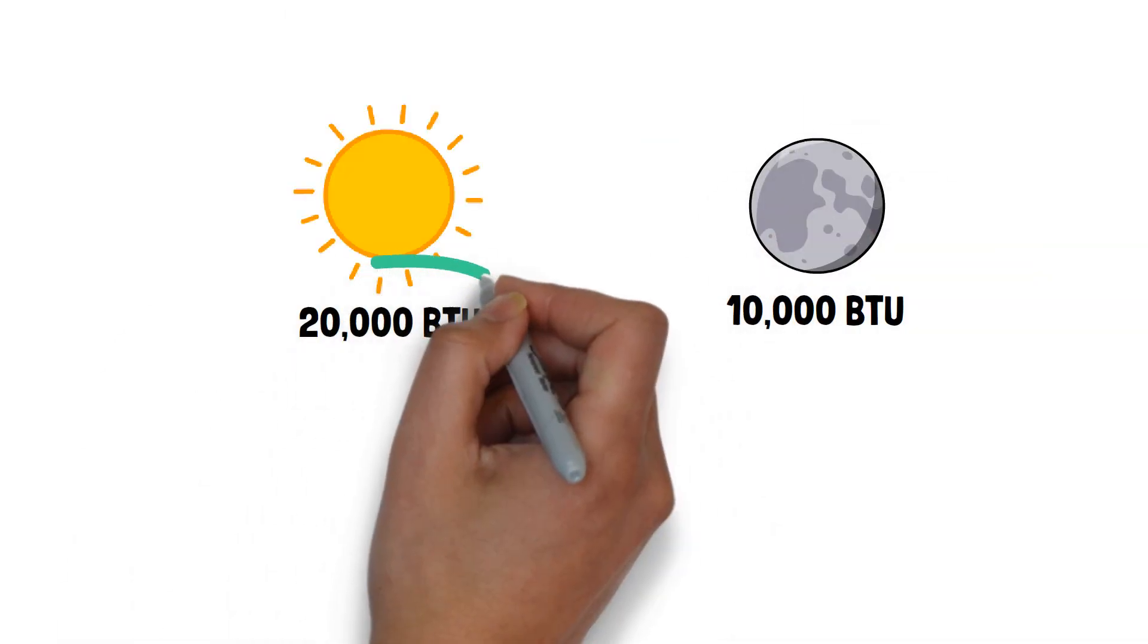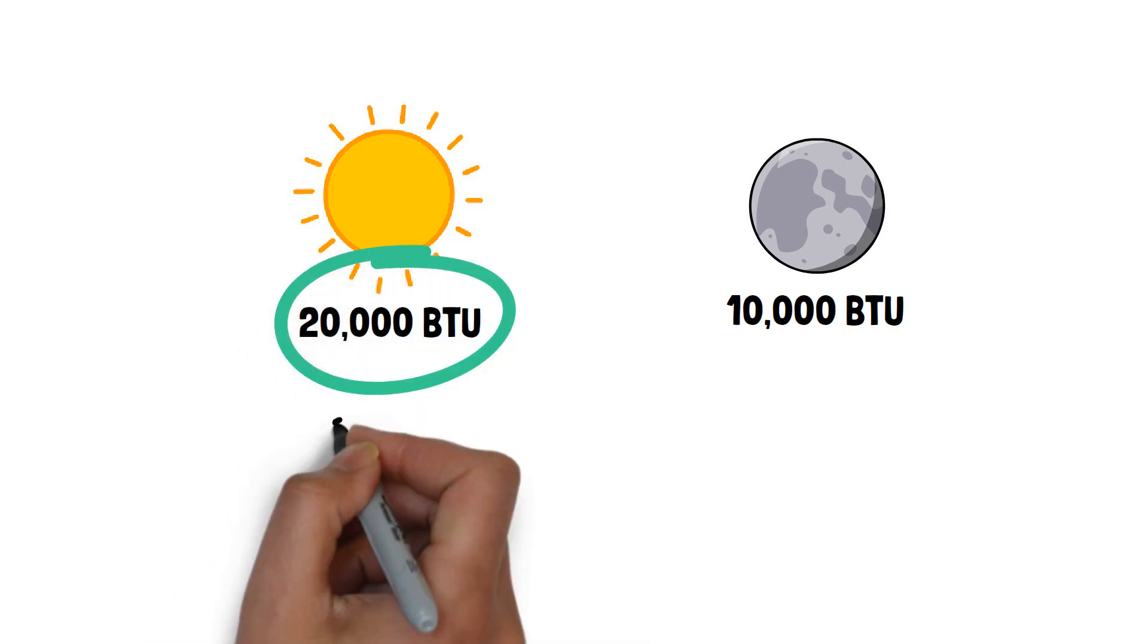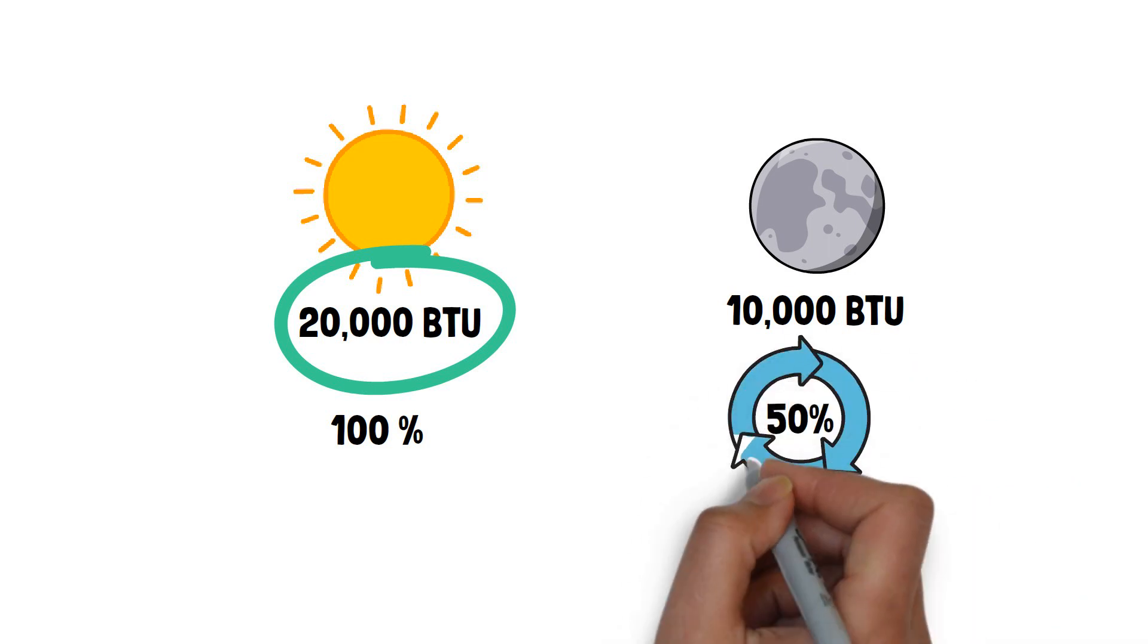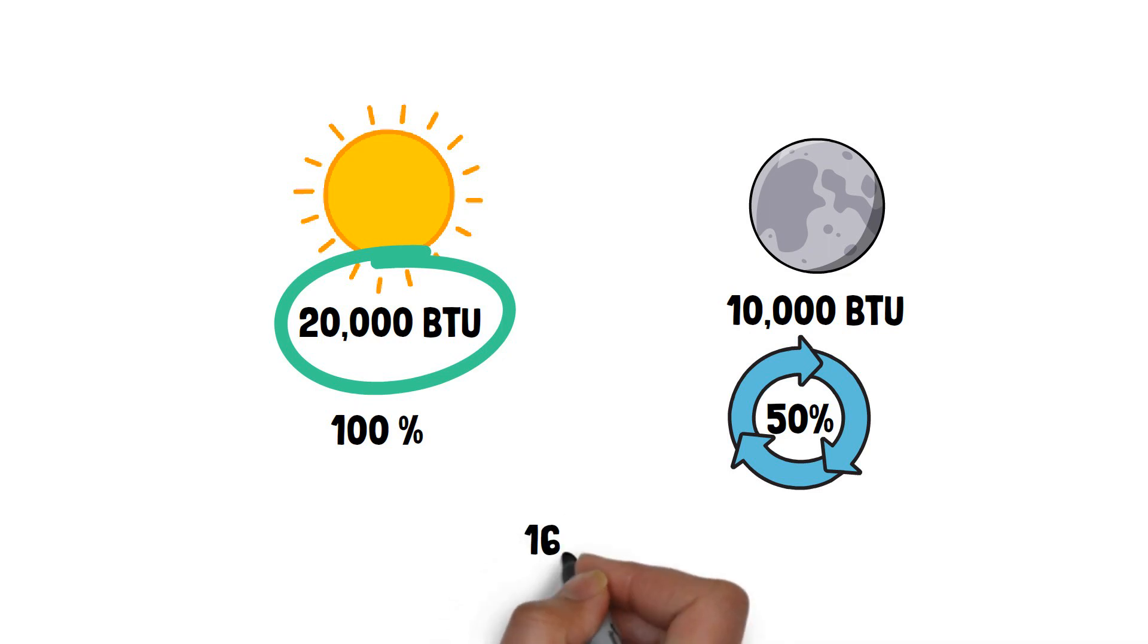Finding a happy medium is the best solution. For example, if your space needs 20,000 BTU during the day and 10,000 BTU during the night and you install a 20,000 BTU air conditioner, it will work 100% of the time during the day and 50% of the time during the night. This can cause quick cycling during the night and may not be energy efficient. The answer is to find a happy medium. For example, opting for a 16,000 BTU. We want our customers to take all of the necessary factors into consideration and make their own decisions based off of their comfort.